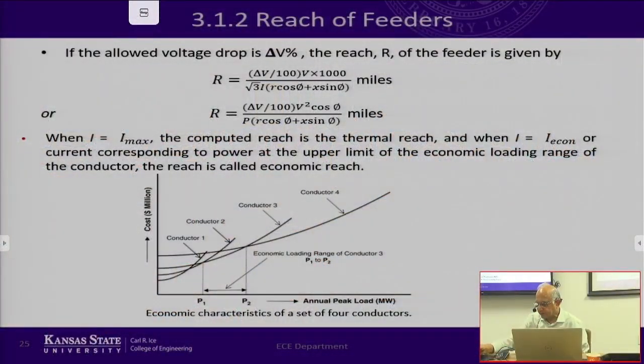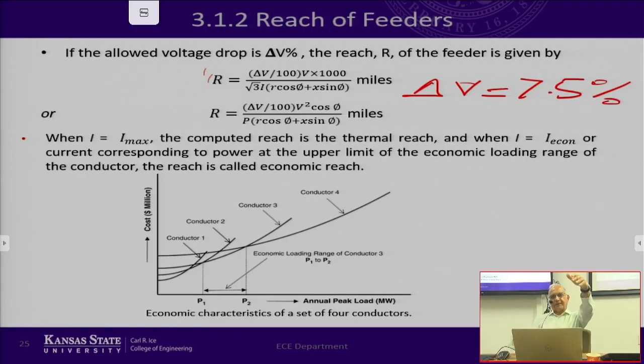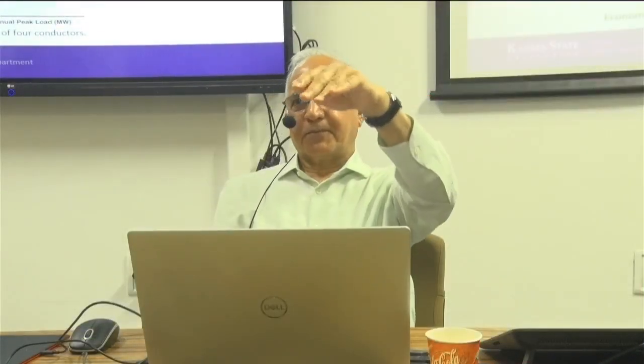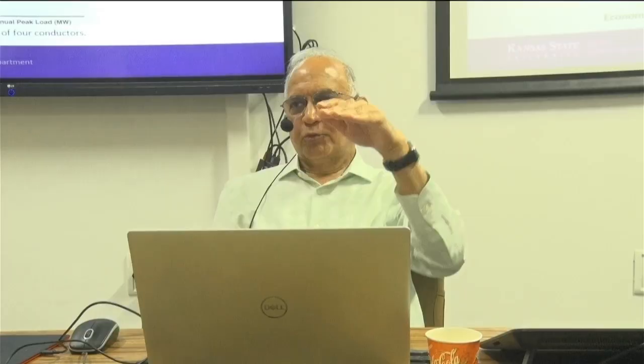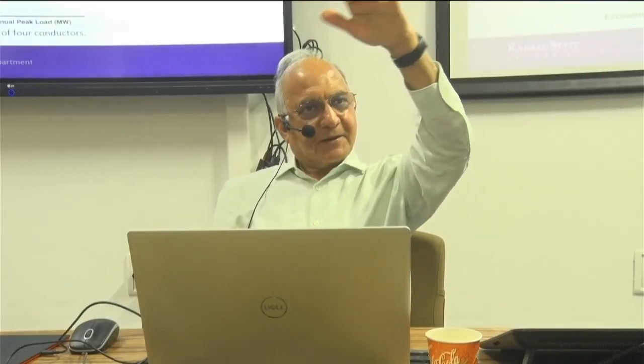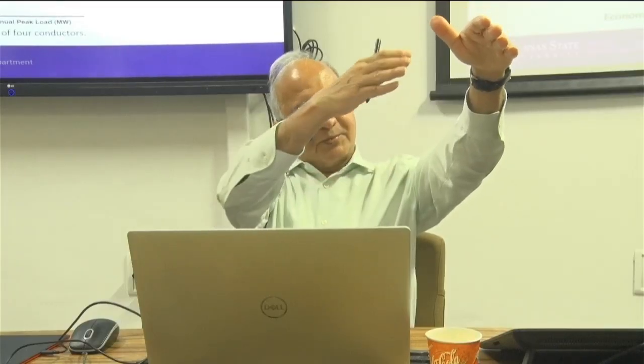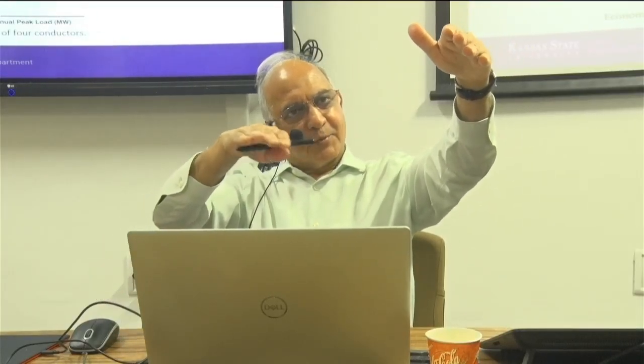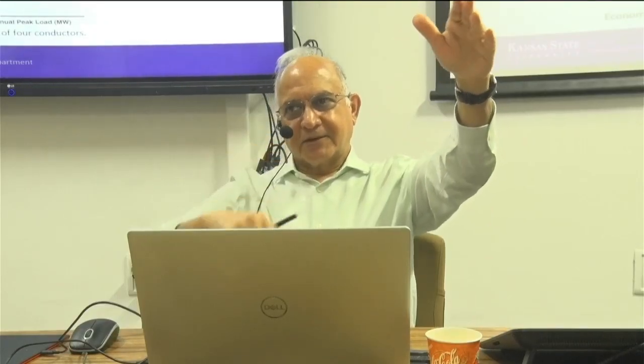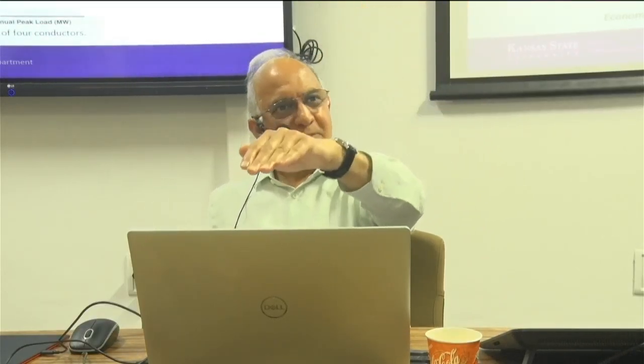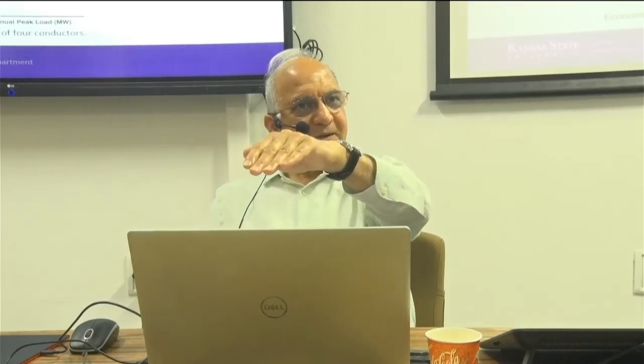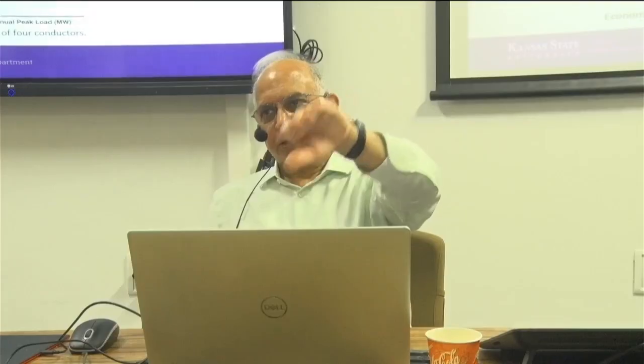The reason is that, as I said, 120 volts is your nominal, and you have plus 5%, minus 5%. Assuming that you are operating at the higher end at the beginning, you can go 10%, but we allow 2.5% as a margin. So with the margin, we allow only up to 7.5%. So that's acceptable. A 7.5% voltage drop is allowed.